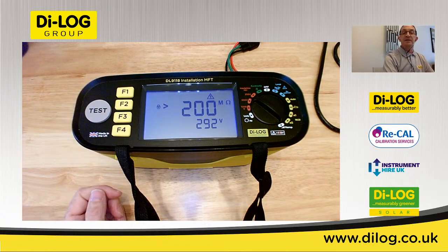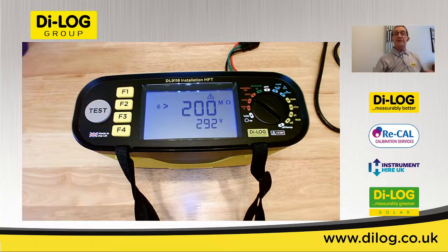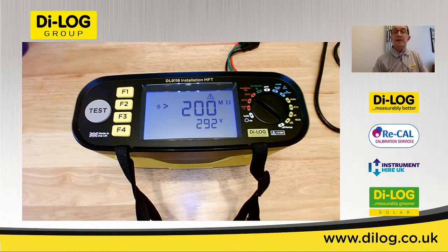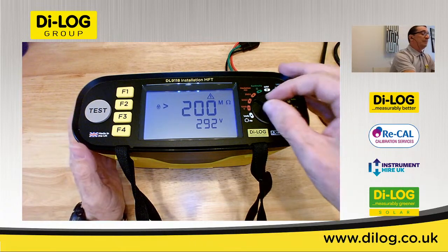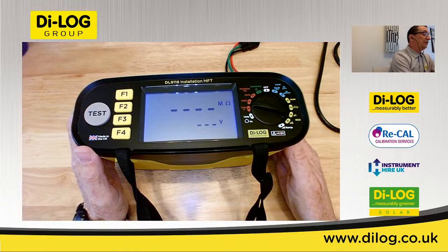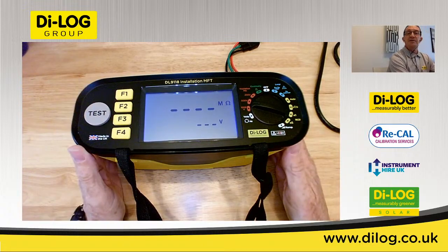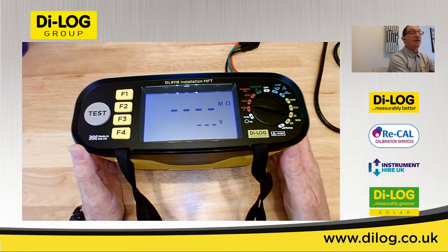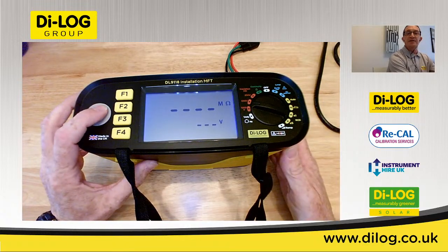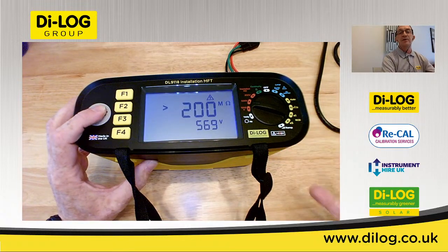The latching facility is very useful if you're asked to do an extended insulation test, which might test a system a little bit longer, looking for any breakdown over a period of time. Switching to 500 volts, the lock symbol is eliminated this time to begin a new test. And to carry out a traditional insulation test, just hold down the button for as long as necessary.